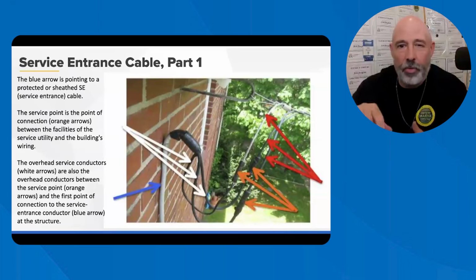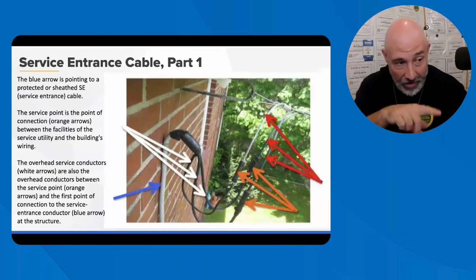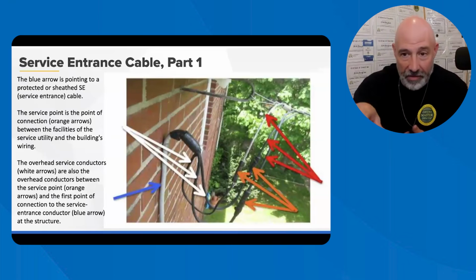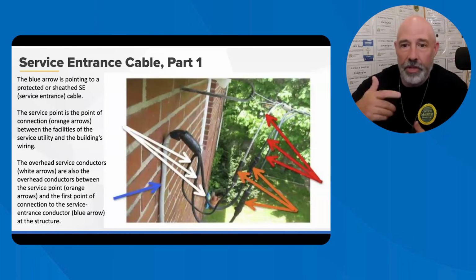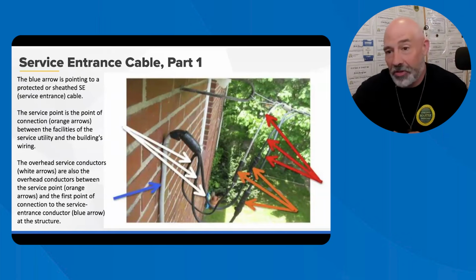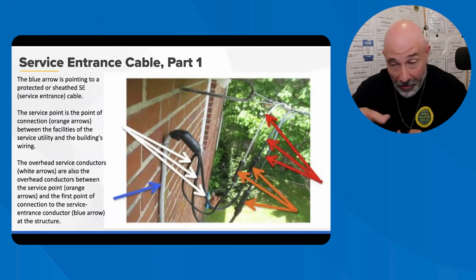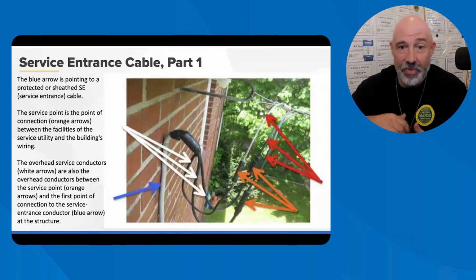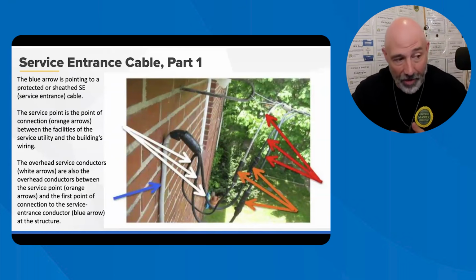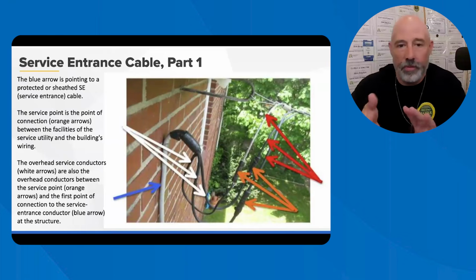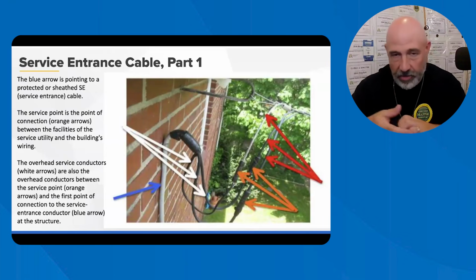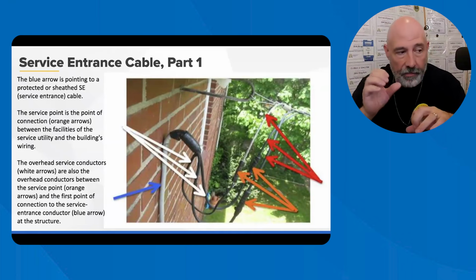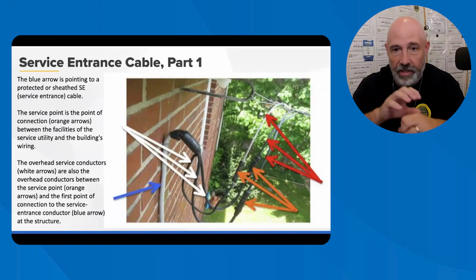The service point is the point of connection. Those are those orange arrows, between the facility of the service utility and the building wiring. The overhead service conductors, those are the white arrows. These are also the overhead conductors between the service point, the orange arrows, and the first point of connection, which is the service entrance conductor. Those are the blue arrows. We're going to go into this a little bit more. It is understood that those are the raceways. Whenever you think of the raceways, I want you to think of the current flying through there, through the conduit and stuff like that. Those are nice raceways.